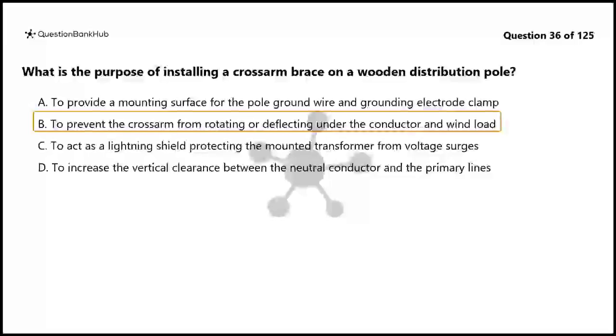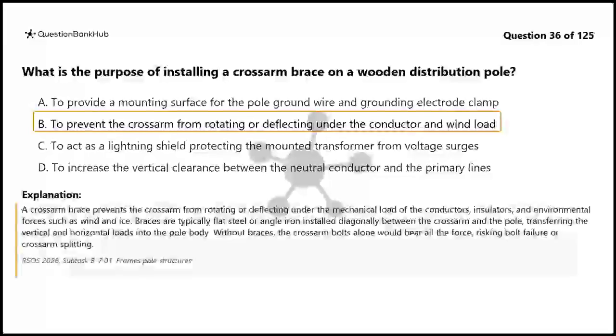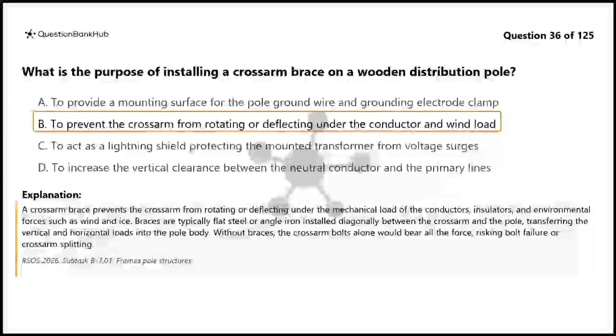The correct answer is B. A crossarm brace prevents the crossarm from rotating or deflecting under the mechanical load of the conductors, insulators, and environmental forces such as wind and ice. Braces are typically flat steel or angle iron installed diagonally between the crossarm and the pole, transferring the vertical and horizontal loads into the pole body. Without braces, the crossarm bolts alone would bear all the force, risking bolt failure or crossarm splitting.